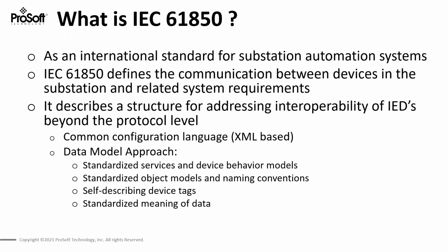So what is IEC 61850? It's basically an international standard for substation automation. It defines not only the communication between the devices, but it also describes and has a structured support for interoperability between various IEDs. They went so far as to define a common configuration language.